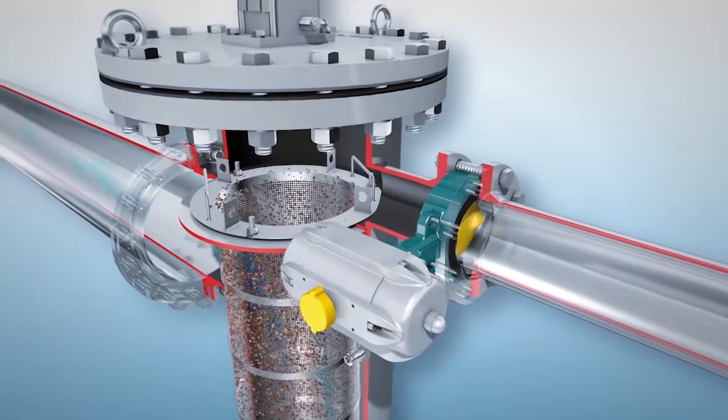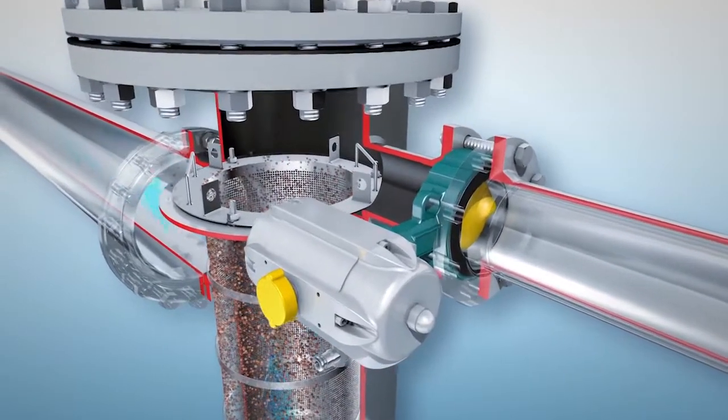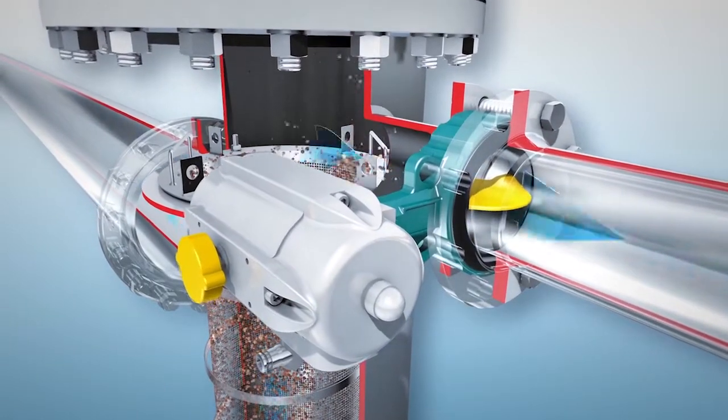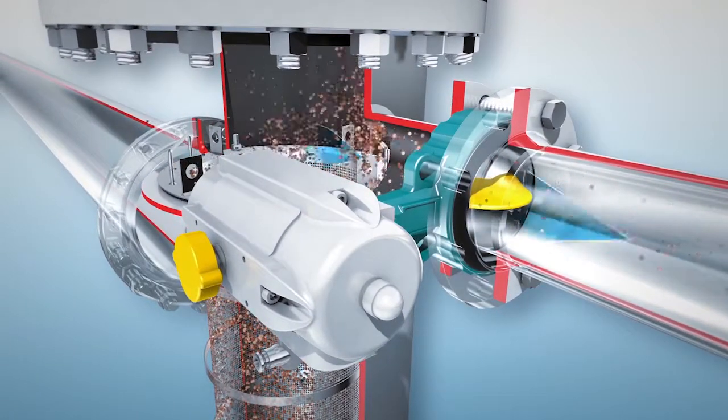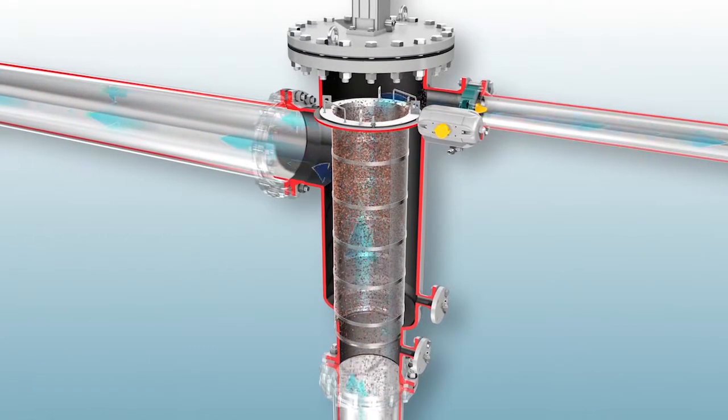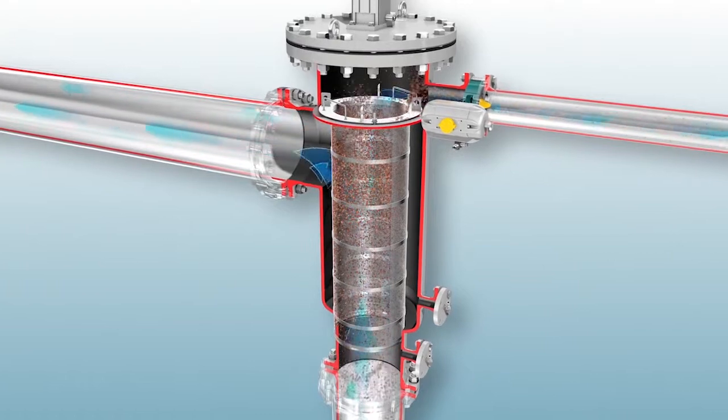Cleaning begins automatically according to a time cycle or after a differential pressure signal by the opening of the back flush valve. After the initial flush, the concentrated cleaning cycle begins when the flushing disc starts its journey down the inside of the filter screen.